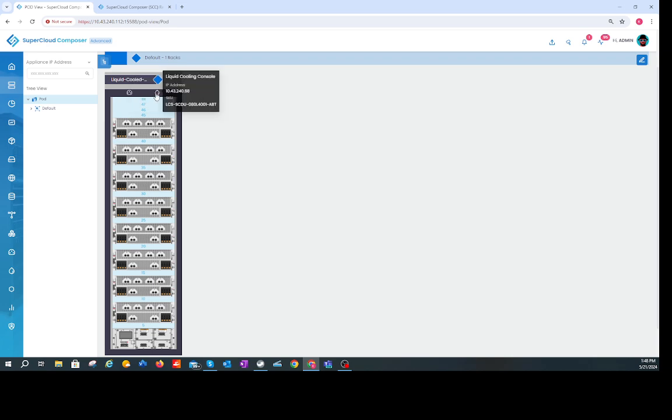And then on the right-hand side, we show it's also managed through a CDU, which is really the brains of the outfit, where water comes through the CDU from an input source and then has a return source. And those are color-coded on the manifold of each of the racks to indicate the supply and return. And by the way, if you get those mixed up, we provide alert management to indicate that the cables are backwards and things like that for that use case.